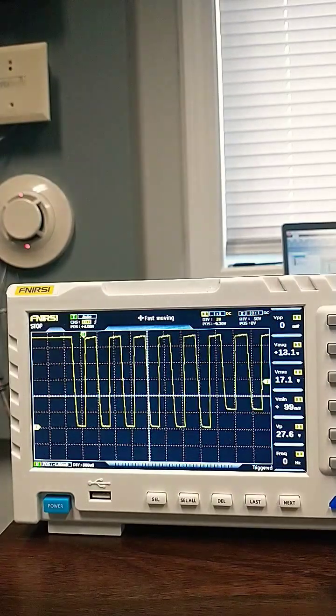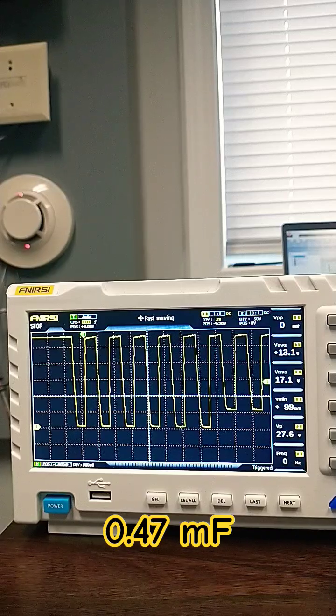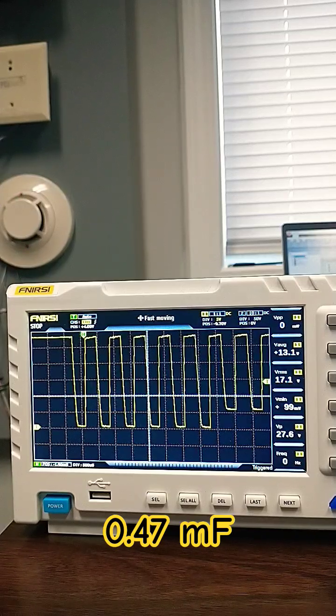Excessive capacitance can distort the waveform. This is how it looks with 0.47 microfarads connected across the SLC.